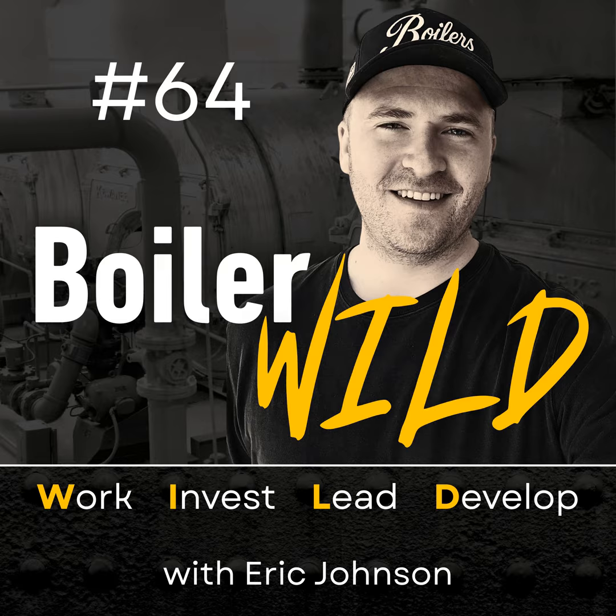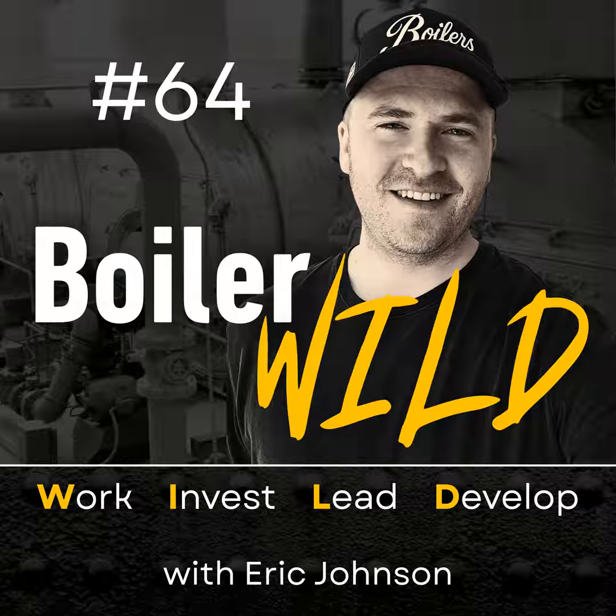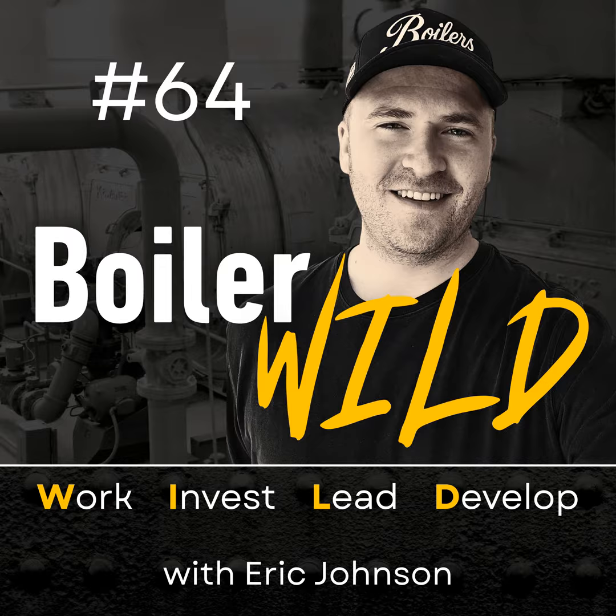So that if the boiler isn't starting, the display can show, hey, this switch and this switch are open. And even if there's an input and output, like green and red lights, they can do that as well. Or they can produce an alarm and say, low gas pressure switch open. Those are all different scenarios for being able to better troubleshoot the issue. But you just need to remember that there are recycle limits and non-recycle limits. But on the more complicated systems, they will typically tell you, hey, this is what opened.